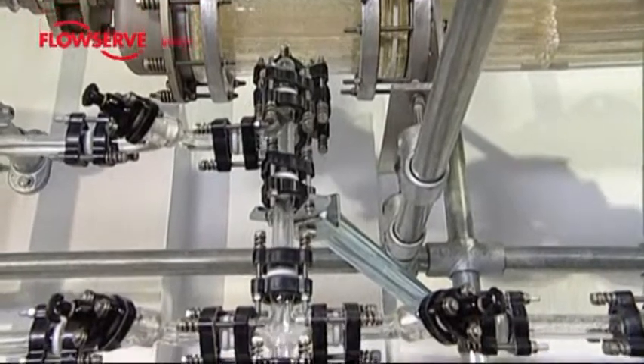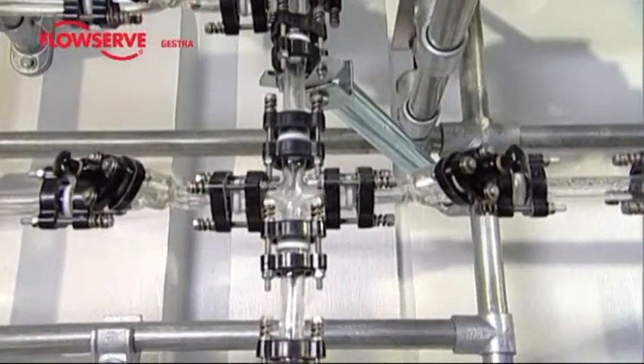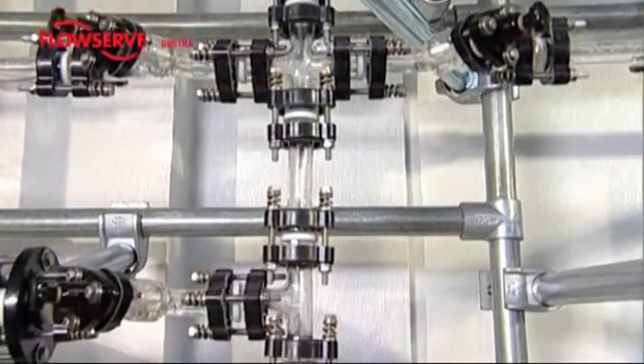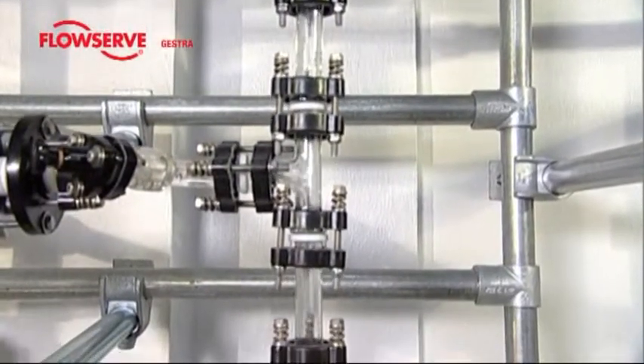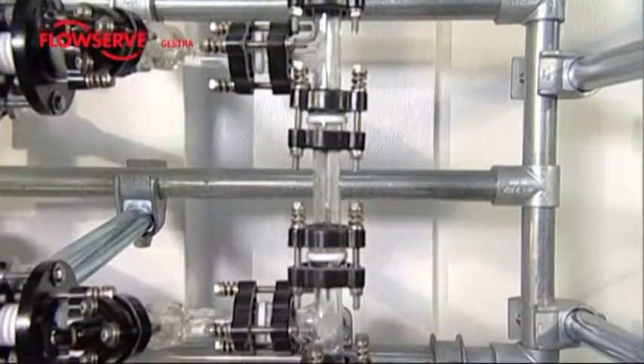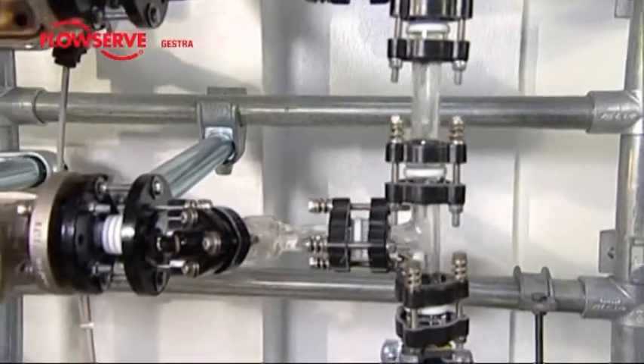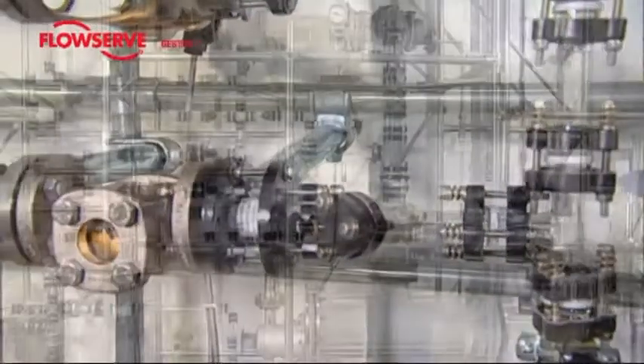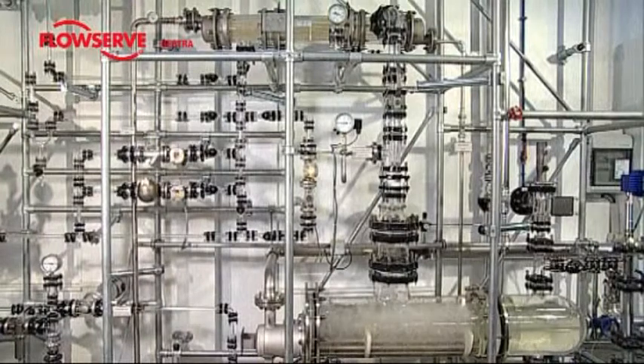An accumulation of condensate in the heat exchanger leads to the dangerous water hammer effect, floods the heating surface and reduces the heat transfer coefficient by a factor of about 4. As a result, it's no longer possible to guarantee that the product passing through the heat exchanger is adequately heated at all times. It's recommended that thermostatic steam traps not be used in the case of large heat exchangers controlled on the steam side.